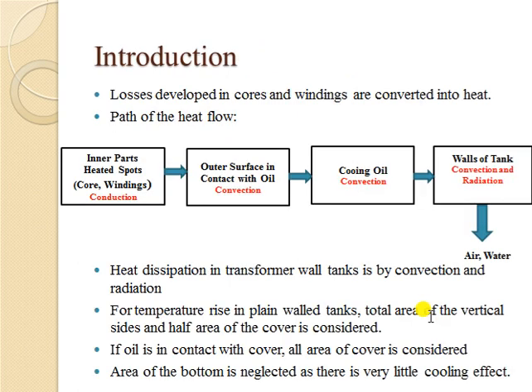Here we are going to understand how heat flows from the inside parts of the transformer to the cooling medium at the outside. Heat is generated during electrical operations — current flows in windings and flux flows in the core — creating heated spots in the inner parts. Through conduction, that heat reaches the outer surface in contact with oil, and then through convection it moves into the cooling oil.